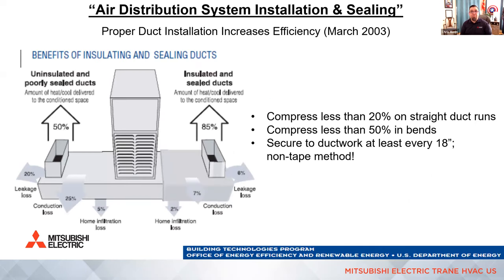All right. A good duct system, believe it or not, loses about 20% or 20 to 25% based on studies done by Energy Star. And this is obviously done by the Department of Energy. So what they say makes a good duct system, you can see, is sealed and insulated correctly to code, compress flex less than 20% on straight duct runs and less than 50% on bends. I say don't use flex on bends, use hard 90s, that'll fix that problem. And then you have to secure the ductwork at least every 18 inches using a non-tape method. This is in the International Mechanical Code, which I think every state in New England abides by, but isn't necessarily always enforced. Building inspectors don't necessarily use that.